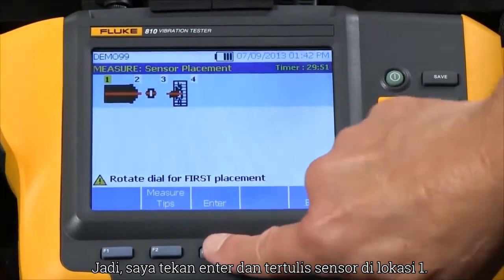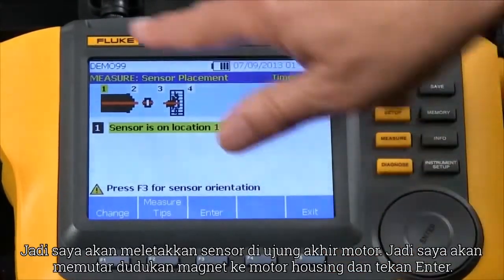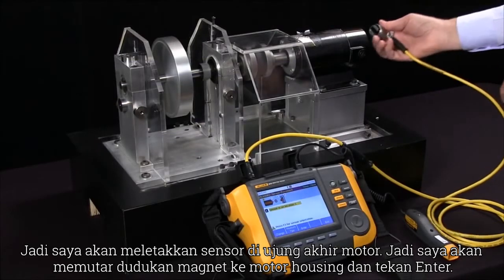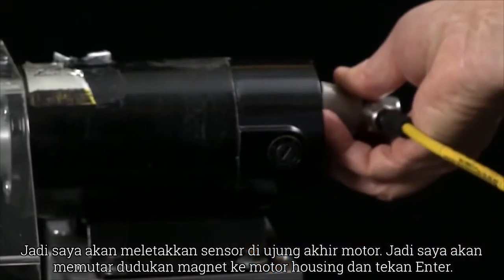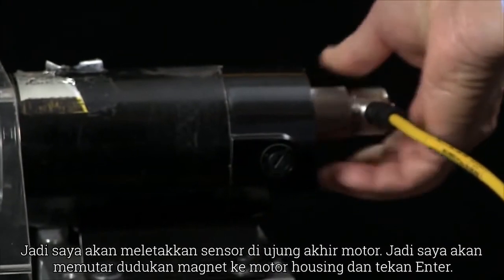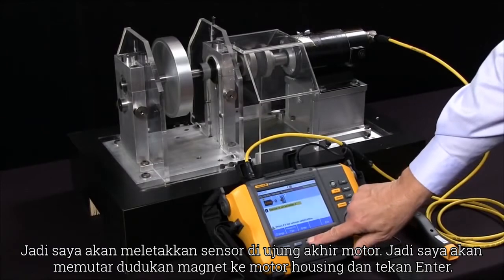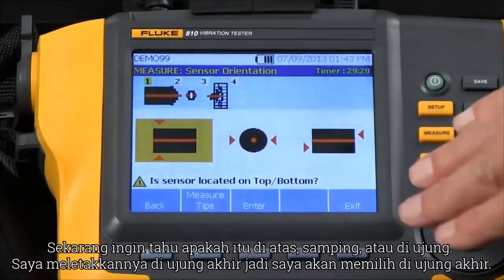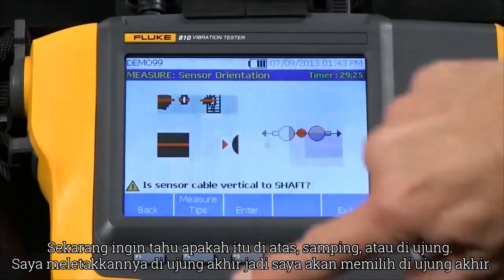I hit enter and it says 'sensor is on location 1' — it wants me to put the sensor on the free end of the motor. So I rotate the magnetic mount onto the motor housing and press enter. Now it wants to know: is it on the top, the side, or the end? I put it on the end, so I'm going to select end.